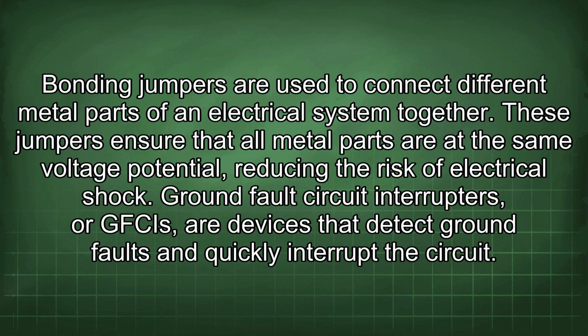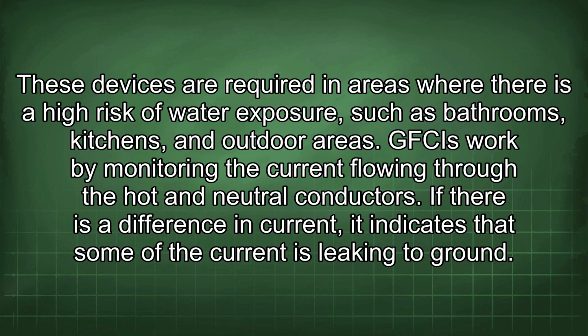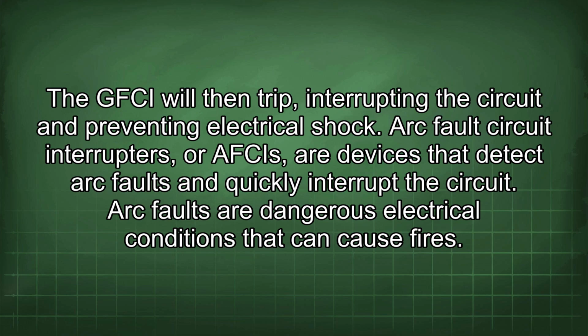Ground fault circuit interrupters, or GFCIs, are devices that detect ground faults and quickly interrupt the circuit. These devices are required in areas where there is a high risk of water exposure, such as bathrooms, kitchens, and outdoor areas. GFCIs work by monitoring the current flowing through the hot and neutral conductors. If there is a difference in current, it indicates that some of the current is leaking to ground. The GFCI will then trip, interrupting the circuit and preventing electrical shock.